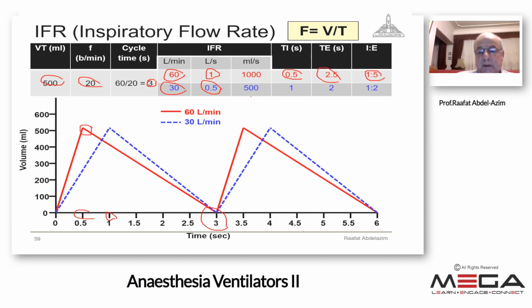If I decrease the flow rate from 60 to 30 liter per minute, this means that the inspiratory time would be 1 second, expiratory time will be 2 seconds, and the ratio is 1 to 2. So the red line is a ventilation at a rate of 20 per minute, having tidal volume of 500. The blue line is the same 20 per minute, same tidal volume, but the inspiratory flow rate is slower. Slowing the inspiratory flow rate means prolonging the inspiratory time and shortening the expiratory time. So the ratio here is different according to each value of inspiration and expiration. If it is not clear, please tell me.